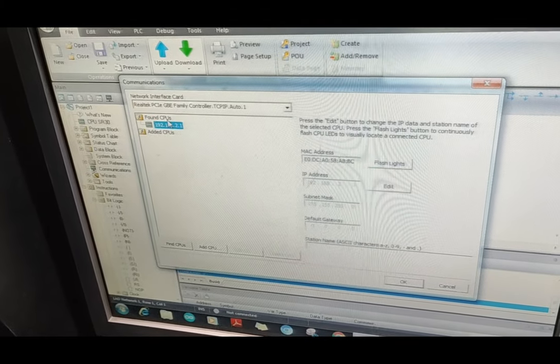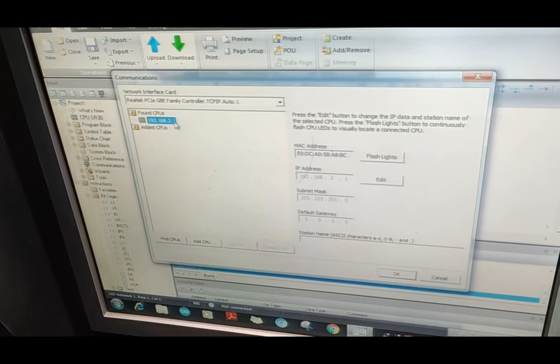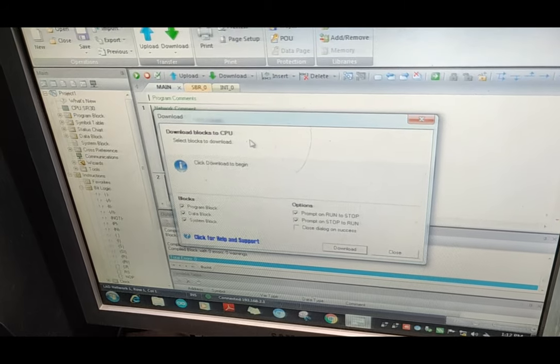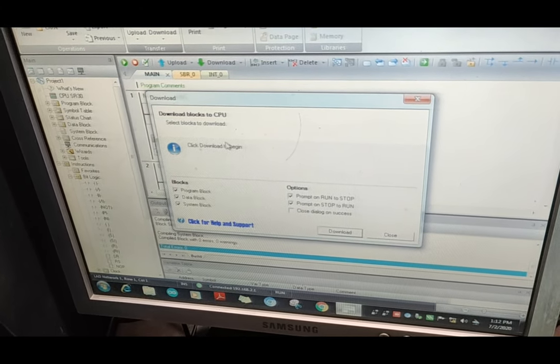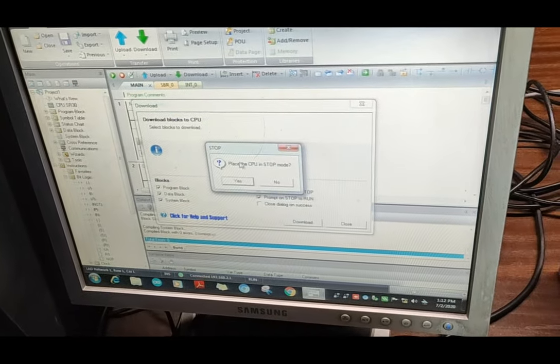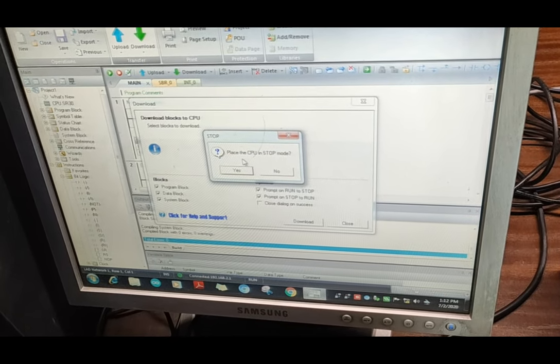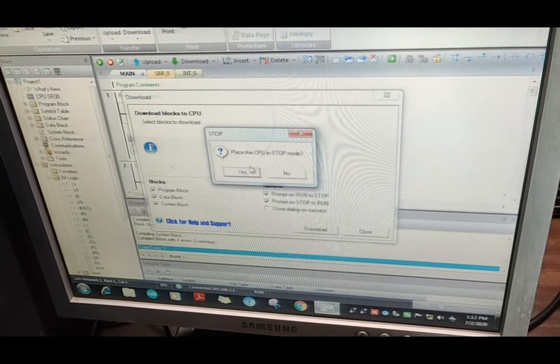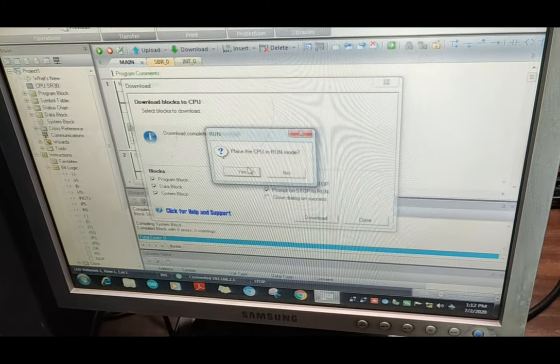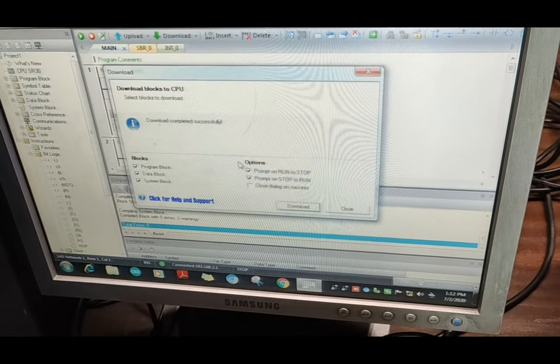We download this program to the PLC using the download button. The communication shows our PLC's IP, which is automatically detected by the software. We press OK. The message shows to download blocks to the CPU, so we press the download button. The program prompts that the CPU is in run mode, so we place the CPU to stop mode first, confirm yes. The program downloads and we turn the PLC back to run mode, confirming yes. Download completed.